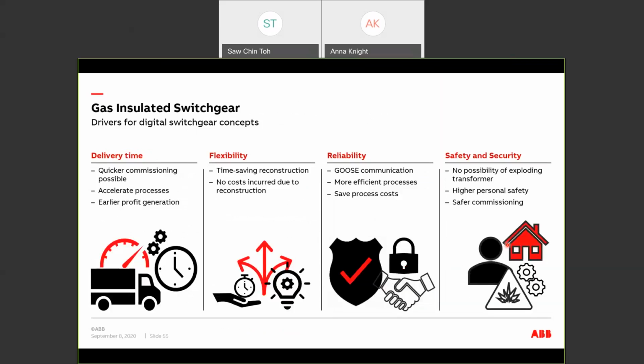So why digital switchgear? Digital switchgear can be delivered faster. The reduction is mainly due to less time taken to clarify or decide on the CT and VT data. With sensors, it provides linear measurement for a wide range of values. One size fits all. For example, if you have a substation initially supplied with 11 kV power, and further down the track you plan to upgrade this to 24 kV, the same sensor can be used with minimal reconfiguration in software.